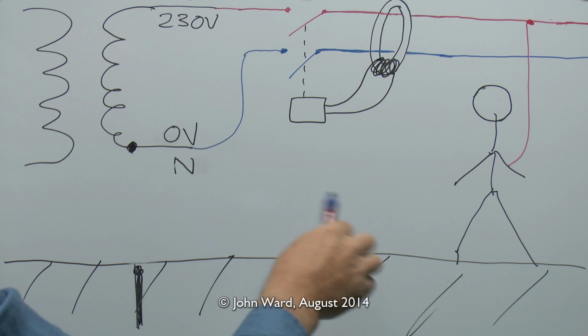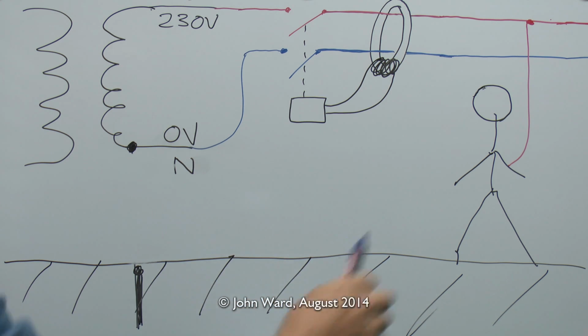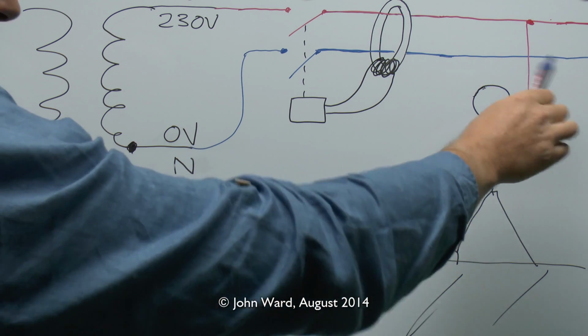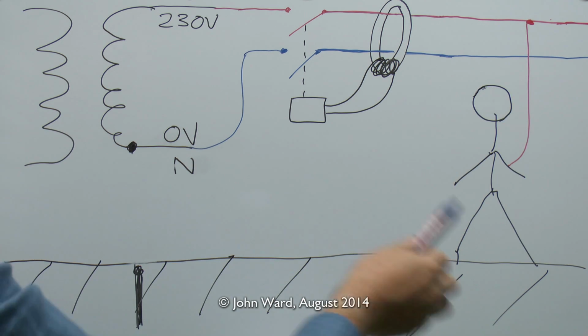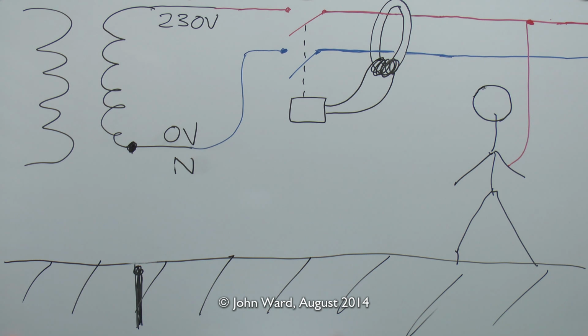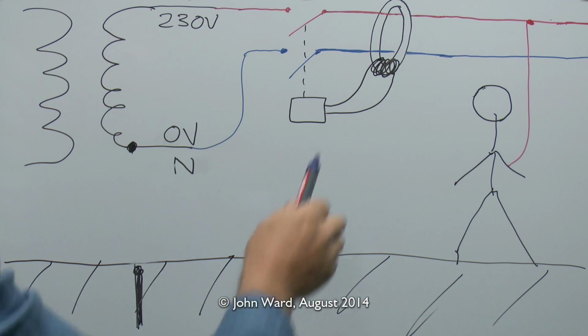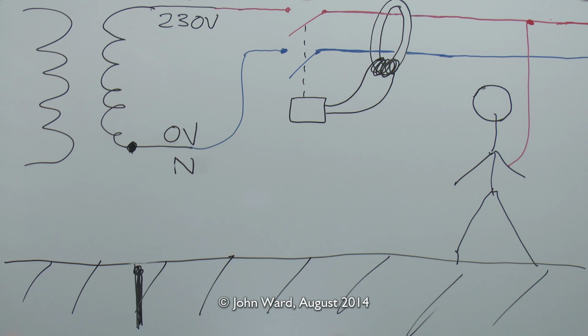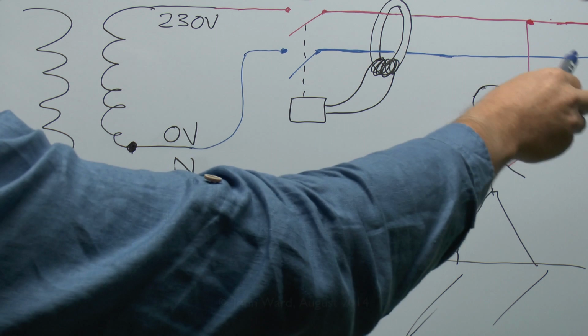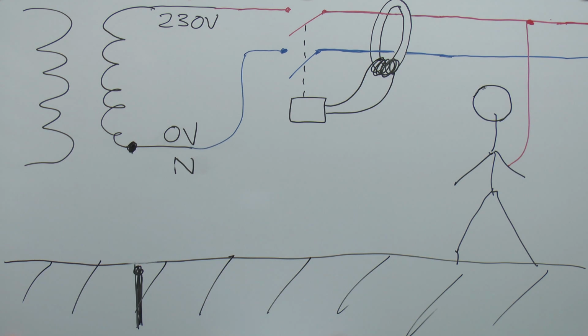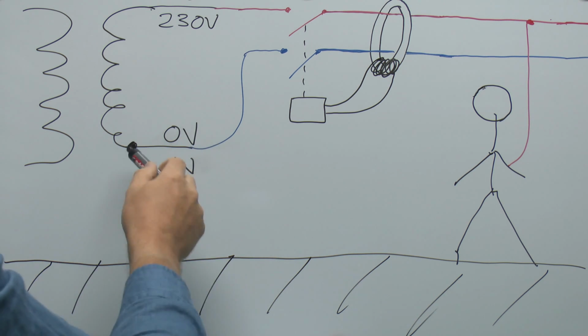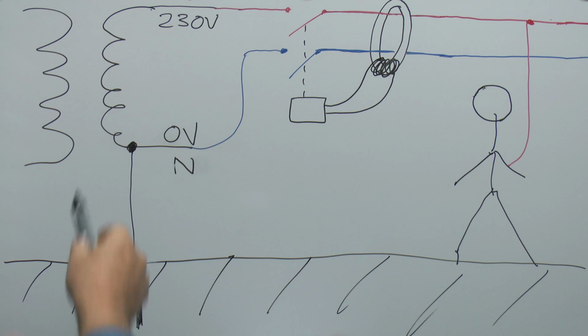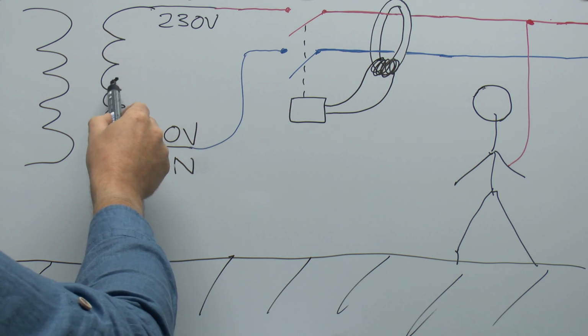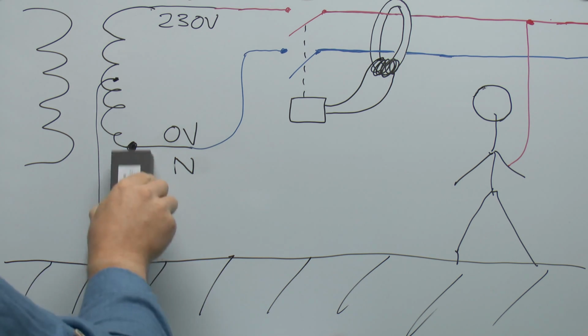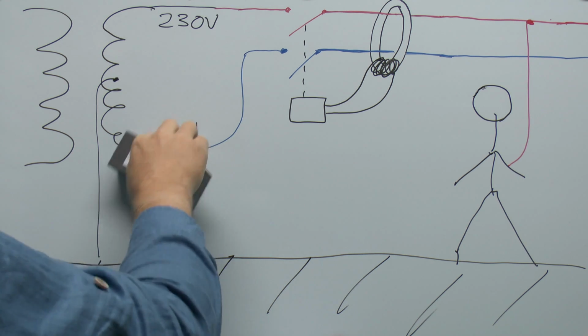this situation is actually fairly dangerous, because any kind of fault on one of the pieces of equipment, on the load side over here, if one of those somehow became connected to ground in some fashion, of course initially you're not going to notice, but as soon as someone then touches one of the conductors elsewhere, they're fairly likely to get a shock, because the path will then go via the person through the other fault that's occurred and of course return back to there. So larger generators would generally have one of the supply lines connected to earth, as in the connection here, or in some cases it might be a centre tapped arrangement, so from the middle of the transformer like that. And obviously that would not exist in that particular case.